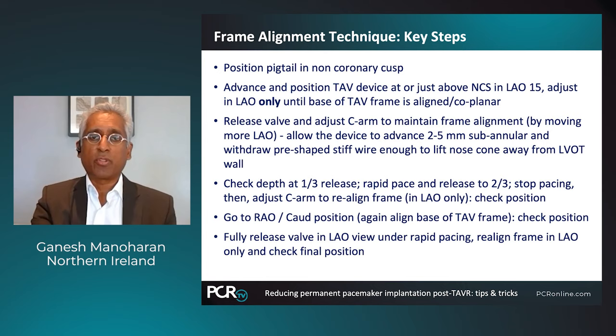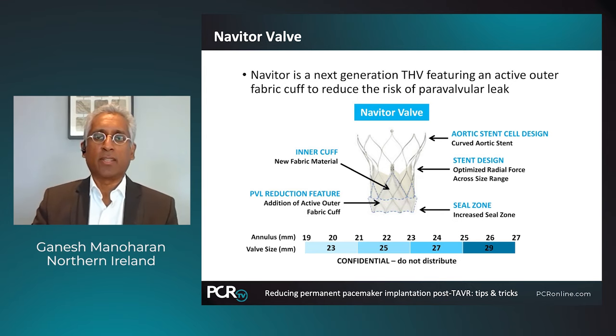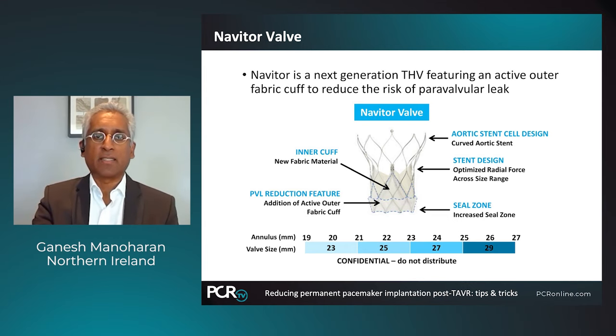Thank you for sharing your techniques. Now we'll see the 30-day outcomes of the Navitor system with the frame alignment technique. I'm going to show you the next-generation Abbott valve — the Navitor valve — and share data that was presented at EuroPCR. The Navitor valve has all the benefits of the Portico device: large frame, self-expanding, resheathable, but it now has an integrated seal zone with an active cuff designed to mitigate paravalvular leak.